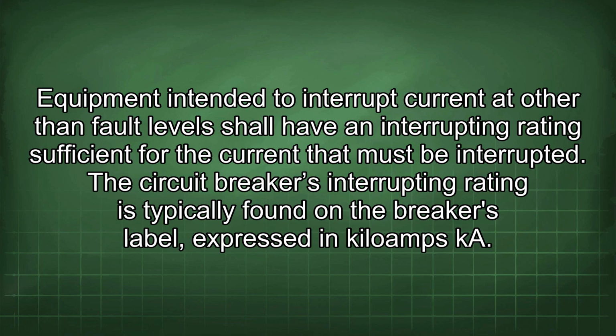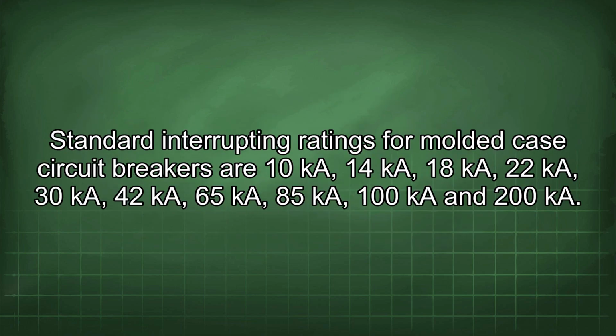Equipment intended to interrupt current other than fault levels shall have an interrupting rating sufficient for the current that must be interrupted. The circuit breaker's interrupting rating is typically found on the breaker's label, expressed in kiloamps, kA. Standard interrupting ratings for molded case circuit breakers are 10 kA, 14 kA, 18 kA, 22 kA, 30 kA, 42 kA, 65 kA, 85 kA, 100 kA, and 200 kA.